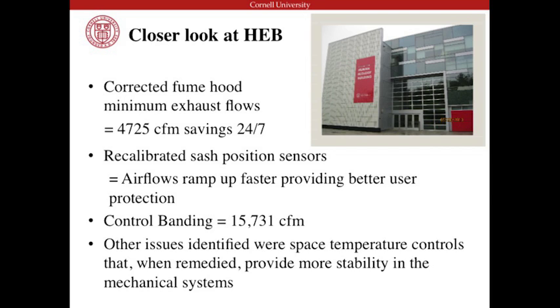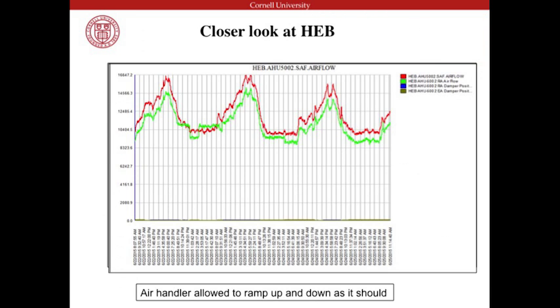There were some space temperature controls in the hallways that, when fixed, provided more stability. Here's an image of the before, showing that instability, and this is what it looked like after — it was actually moving up and down in a much smoother fashion, which is what we want to see.